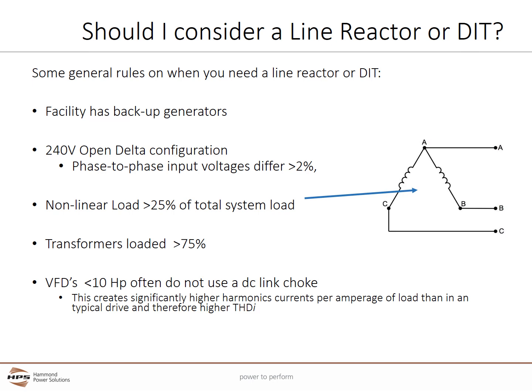Often an indication you have an open delta circuit is when there are two can-style transformers on the line feeding the system. If the system's total nonlinear load exceeds 25% of the system's total potential load, line reactors and DITs should be considered for each VFD. If transformers are heavily loaded above 75% for extended periods of time, harmonics can cause dangerous heating. Line reactors and DITs should be used to reduce this heating. DITs are inherently designed to be able to handle the extra heating caused by poor power quality in VFD-created harmonics.